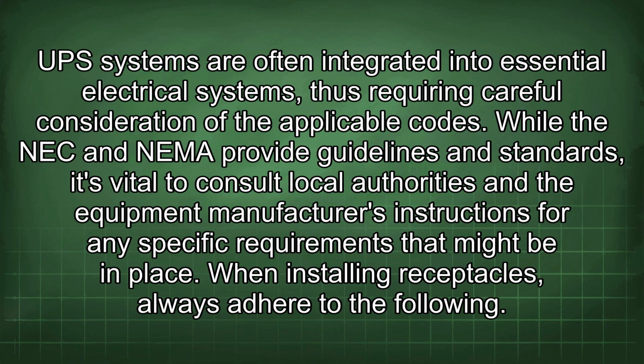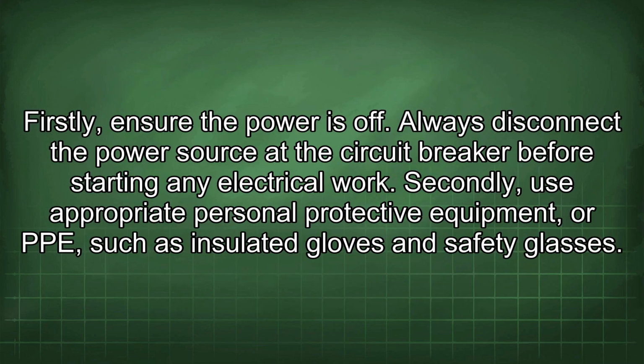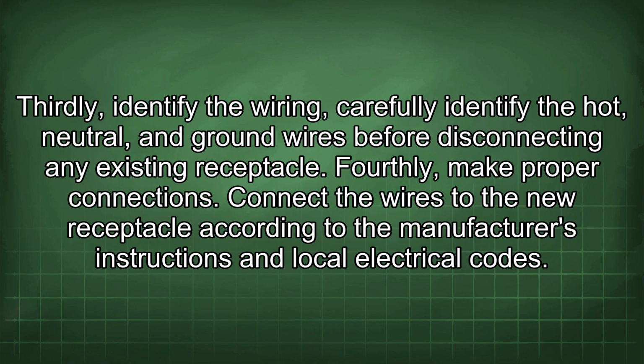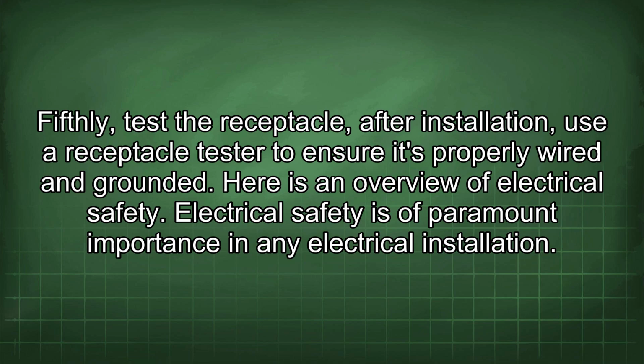When installing receptacles, always adhere to the following. Firstly, ensure the power is off. Always disconnect the power source at the circuit breaker before starting any electrical work. Secondly, use appropriate personal protective equipment, or PPE, such as insulated gloves and safety glasses. Thirdly, identify the wiring. Carefully identify the hot, neutral, and ground wires before disconnecting any existing receptacle. Fourthly, make proper connections. Connect the wires to the new receptacle according to the manufacturer's instructions and local electrical codes. Fifthly, test the receptacle. After installation, use a receptacle tester to ensure it's properly wired and grounded.